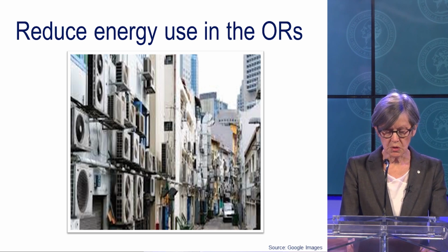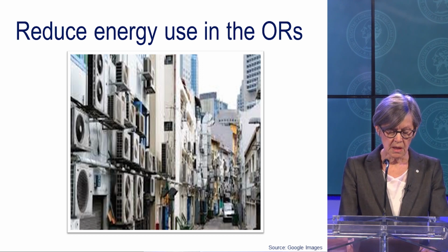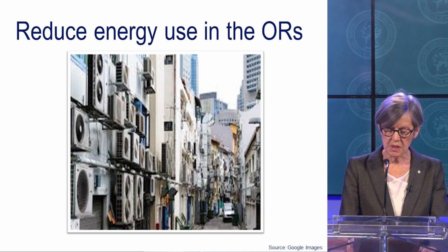The first intervention for greening operating rooms is reducing unnecessary energy use in the ORs. More than half of healthcare's carbon footprint comes from energy use, and the most energy intensive part of the hospital is the operating room. Operating rooms use 3 to 6 times more energy per square foot than the hospital as a whole. This is largely due to use of heating, ventilation, and air conditioning systems, commonly referred to as HVAC systems, as well as the fact that operating rooms are usually left on full capacity 24 hours a day, 7 days a week.